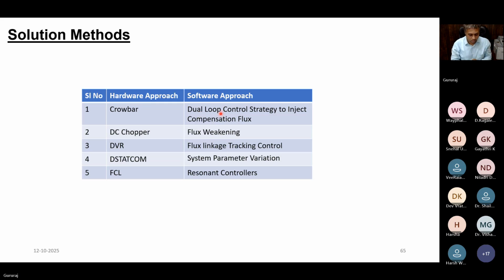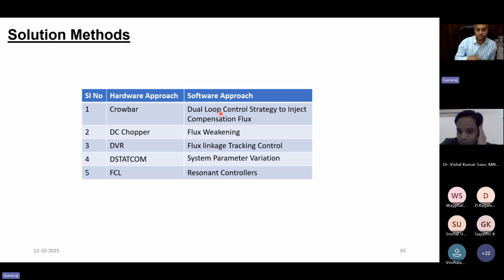you basically offer a compensation flux. What is happening is there is a magnetizing component of flux being produced during the fault, right? And that is the reason why you're generating the voltage. There is more voltage being seen on the rotor side. So you produce a counter flux with the help of the rotor side converter or grid side converter, and try to kill the magnetizing fields, actually. Magnetizing flux. And that's how you do it. And the flux weakening is also a similar approach. So these are the software approaches, which are also seen here in the literature.